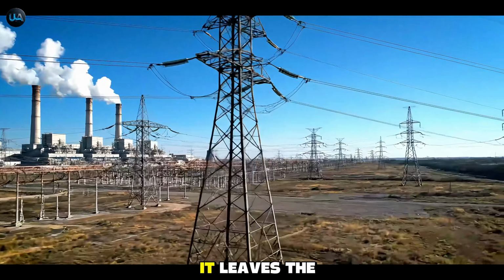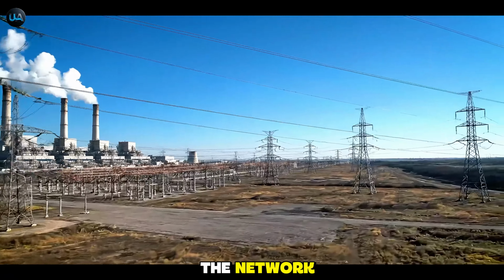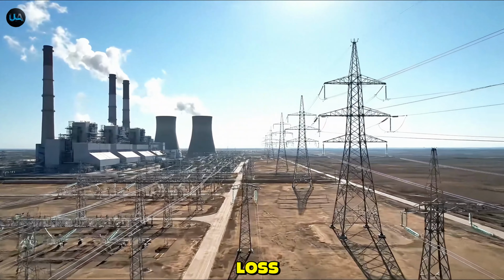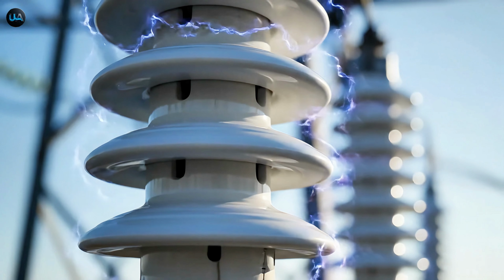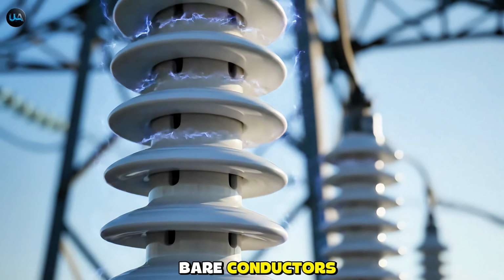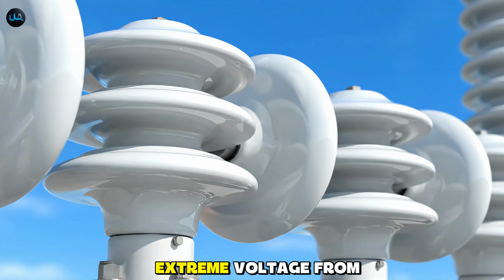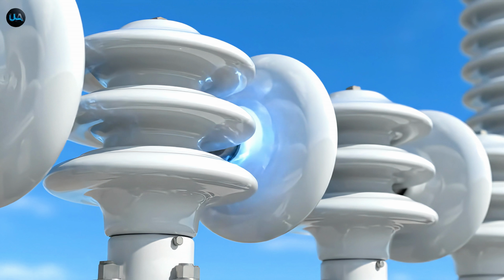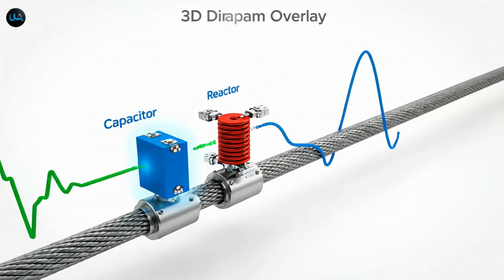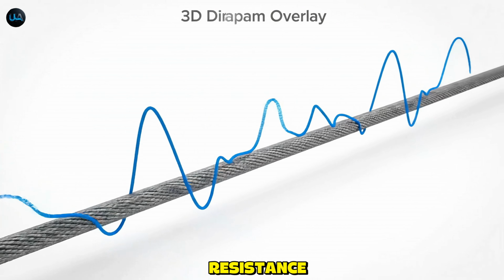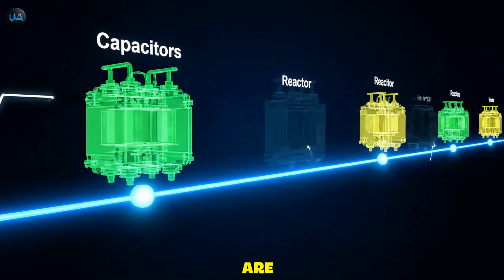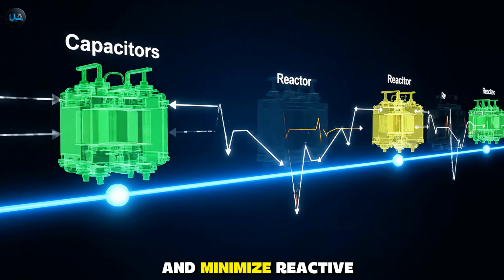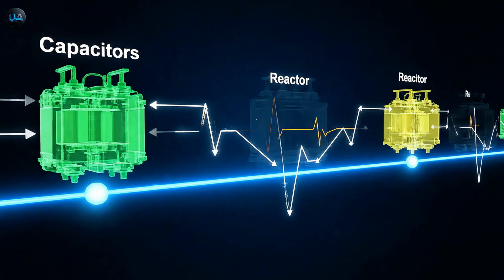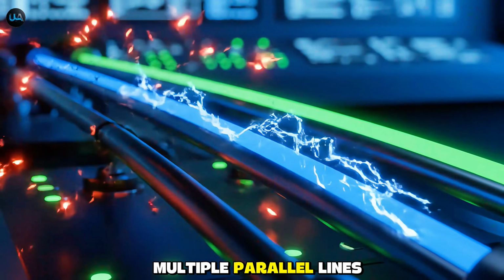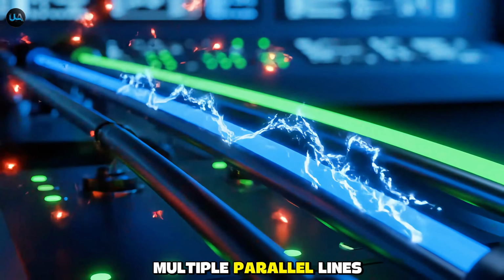Once the power is stepped up, it leaves the plant and enters the transmission system, the network designed for maximum distance and minimum loss. The high-voltage lines are often bare conductors, suspended by massive insulators that prevent the extreme voltage from arcing to the grounded tower. Even high-voltage lines face resistance, so series capacitors and shunt reactors are strategically placed to condition the power and minimize reactive losses. The grid uses multiple parallel lines for redundancy and reliability. If one line fails, power is automatically rerouted through others.